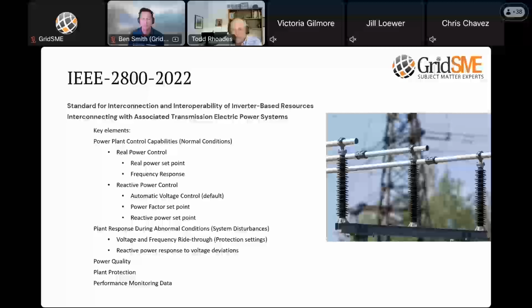And then you have your protection aspects, your voltage and frequency ride through protection settings, ensuring that we allow the system the opportunity to respond to the changes in output and see if the system will recover before tripping. There are also aspects of power quality, general plant protection, and then there is a section on performance monitoring data: what information is critical or important to be able to really evaluate whether the plant is performing in the way it's intended, and if not, can we identify what aspects are not performing in that realm.